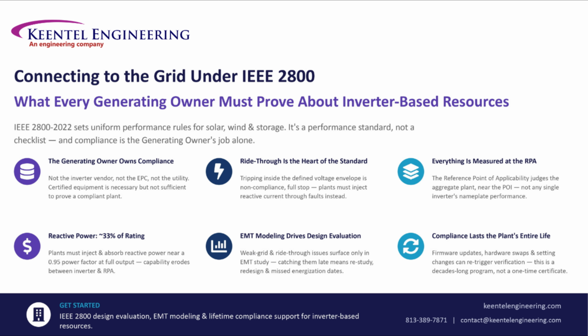Getting there takes real engineering, EMT modeling to catch weak grid and ride-through issues before they become expensive redesigns, and careful attention to reactive power capability, since it can erode significantly between the inverter terminals and the RPA. And compliance doesn't end at commissioning. Firmware updates, hardware swaps, even setting changes down the road can re-trigger verification requirements. This is a decades-long program, not a one-time certificate you file away.